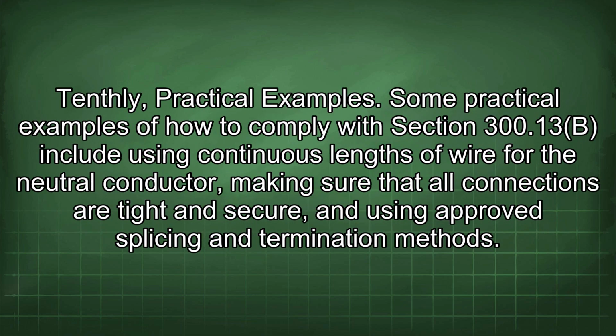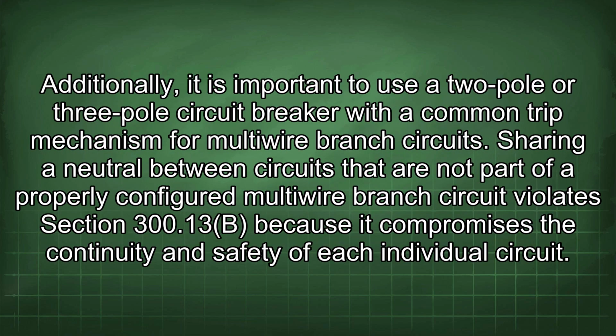Tenthly, practical examples. Some practical examples of how to comply with Section 300.13b include using continuous lengths of wire for the neutral conductor, making sure that all connections are tight and secure, and using approved splicing and termination methods. Additionally, it is important to use a 2-pole or 3-pole circuit breaker with a common trip mechanism for multiwire branch circuits.